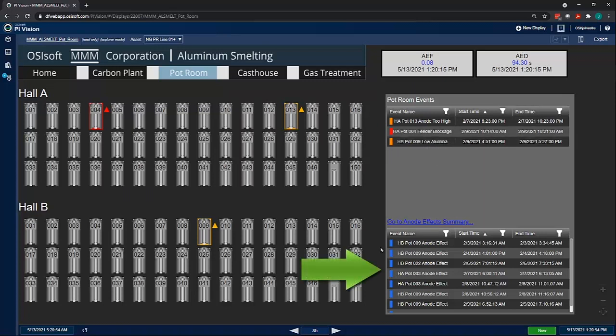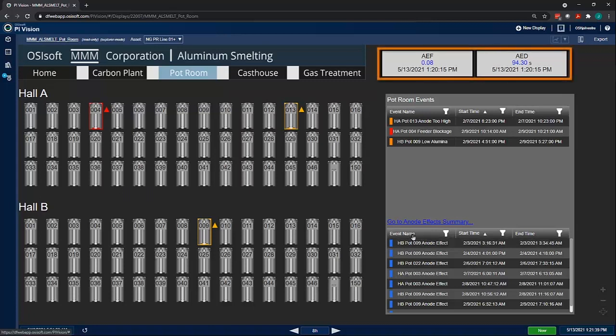Here on the bottom right-hand side, there is an events table that summarizes all the anode effects occurrences, which is a key indicator of the process performance. The PI System is used to determine when an anode effect occurs by looking at the current and the voltage. The frequency and duration of these events are used to create the anode effect frequency and anode effect duration KPIs.